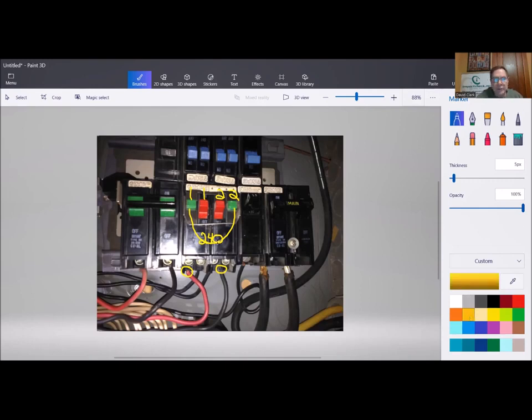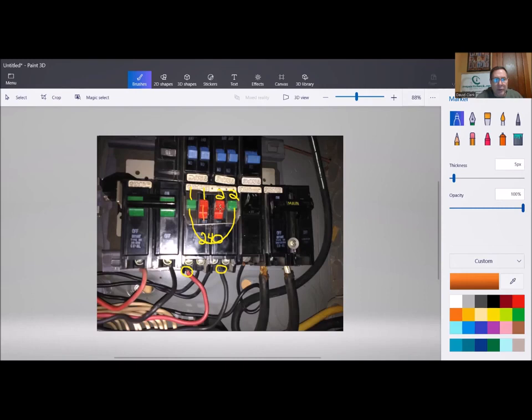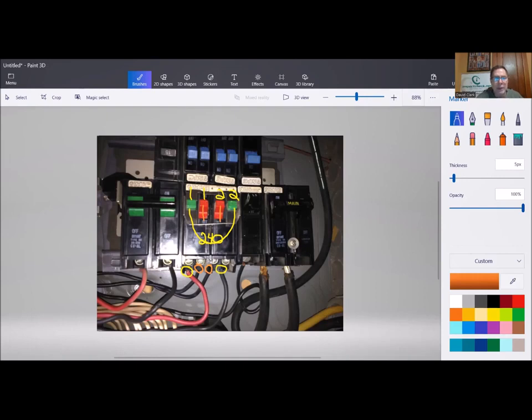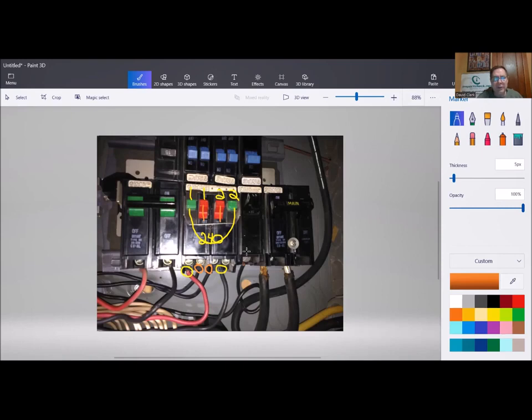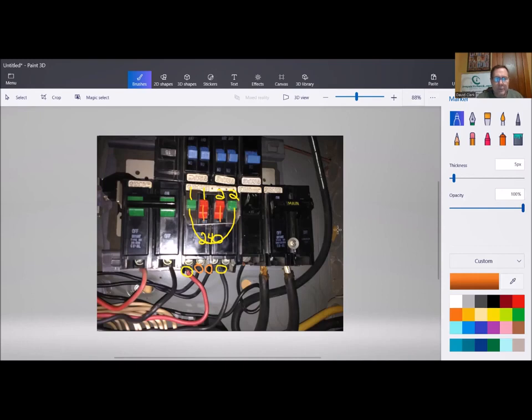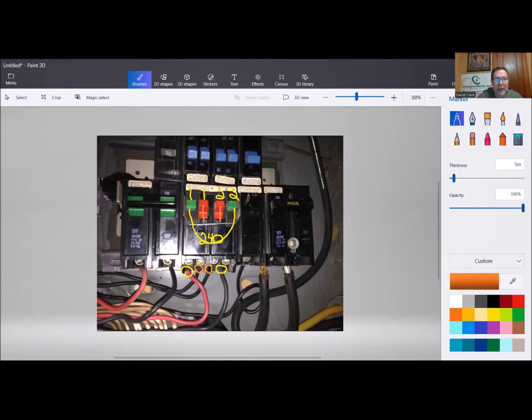So let's switch over to this color orange. Now here's another, this is 120 volts, and this is 120 volts. And you'll see the connections are right here for that. So this is a 20 amp breaker, so that should be a 12 gauge wire going off to where it goes. These are not connected. So they'll trip independently. This is an independent trip breaker. These are connected just externally, not internally, but that handle would cause that to trip. Hopefully, there has been some issues with that not happening, depending on the age. But that's basically how it works. That's a quad breaker, quad plex, whatever you want to call it. And so we've taken just two spots and created a 240 volt and two 120s. So basically I have three circuits here in what would be two spots, but then one of those being a 240 volt.